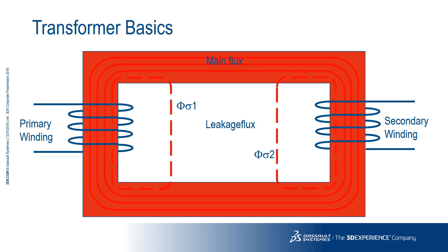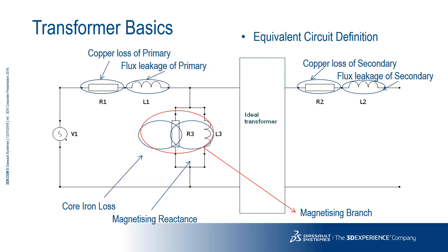But in the real world, you have less than 100% flux linkage. Hence, you have flux leakages to consider in both the primary and secondary. When designing a real-life transformer, a certain amount of leakage may be desirable when designing air gaps or magnetic bypass shunts to limit short circuit currents. In addition to the leakage flux, the coils will be made of less than perfect conductors, so you have copper losses to deal with.